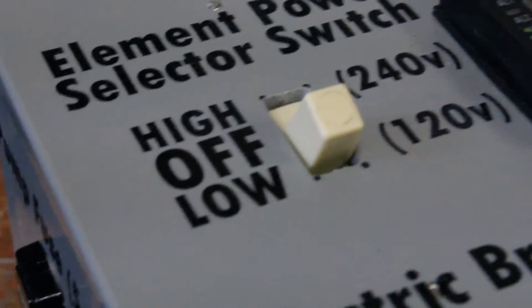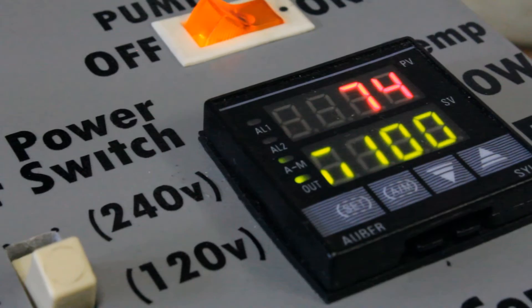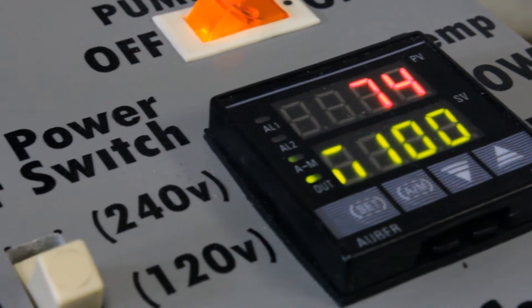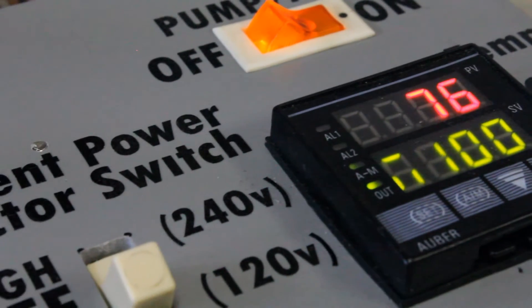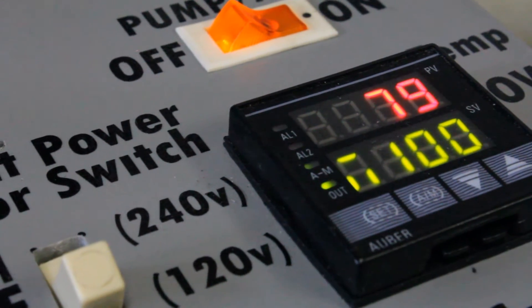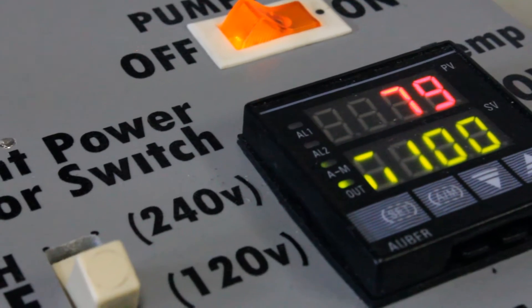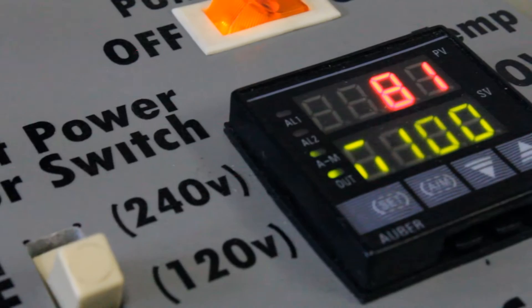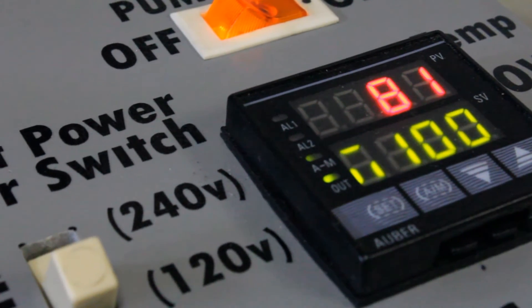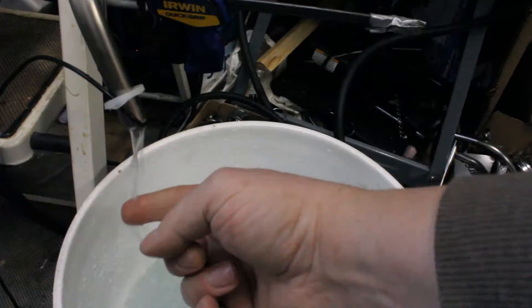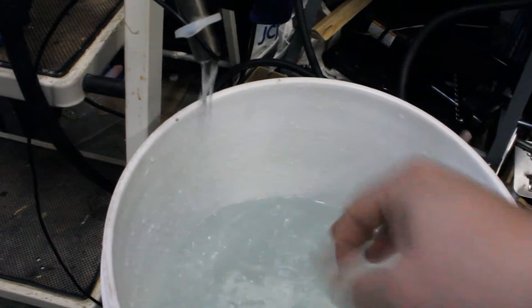It lagged behind a little bit because it takes a little while for the element itself to heat up. Based on the fact that we're feeding this with a constant input temperature water and that the element is staying on 100% of the time and we're not changing the flow rate, once this settles into a certain output temperature it will not change.